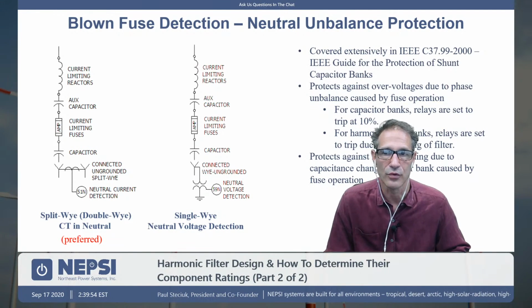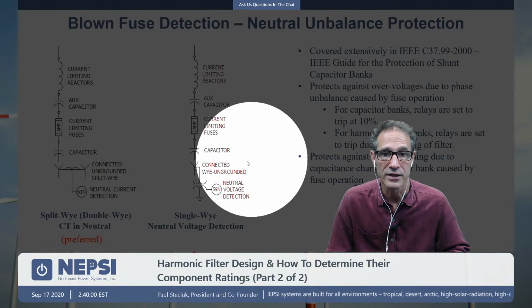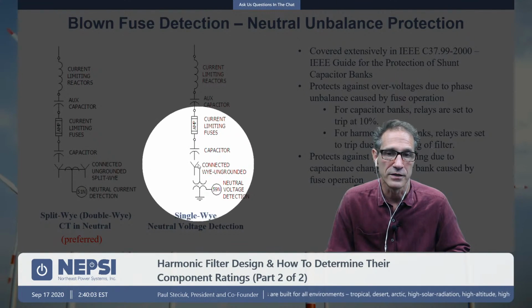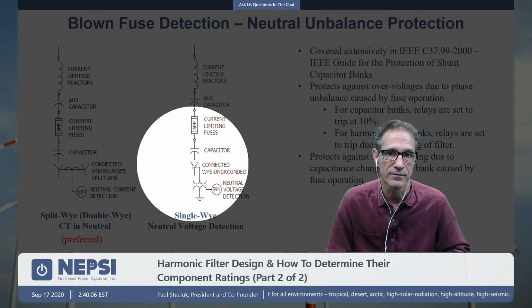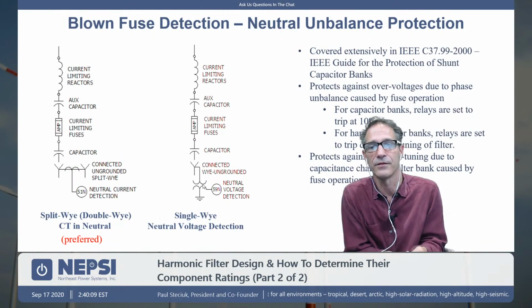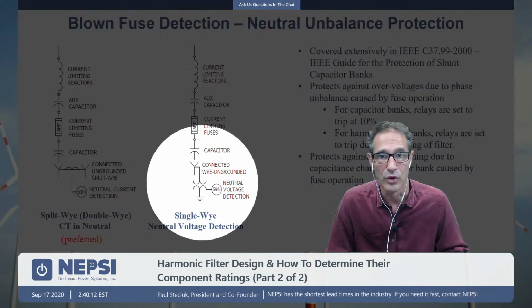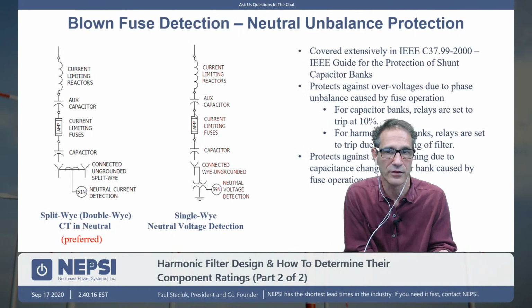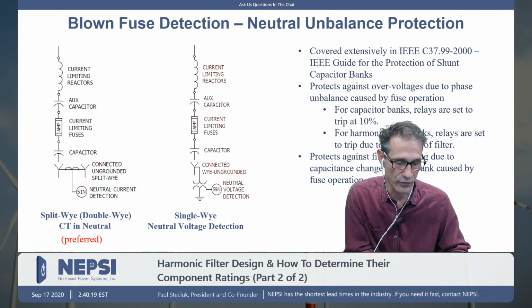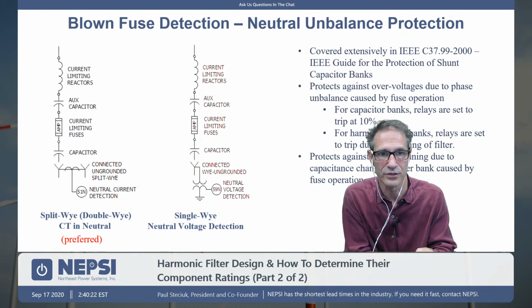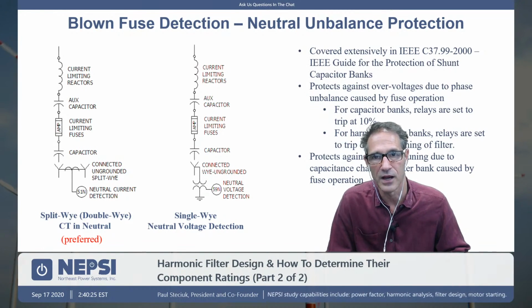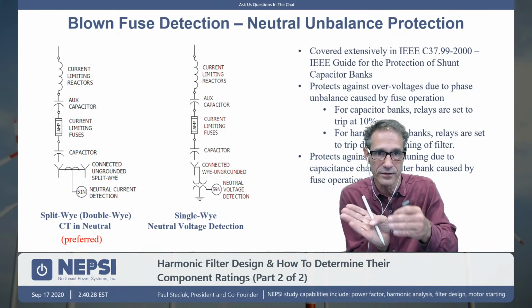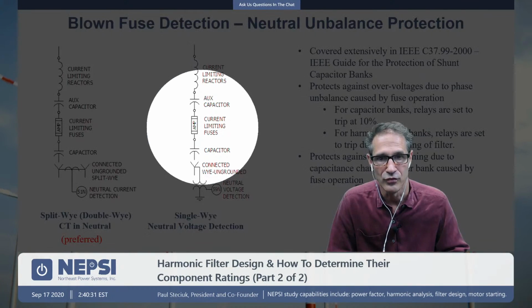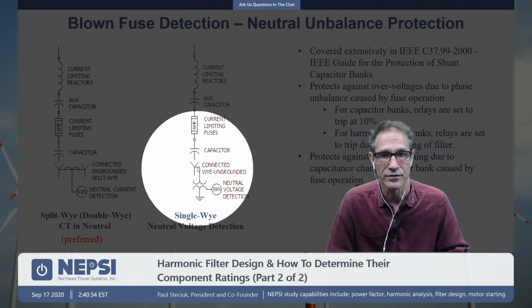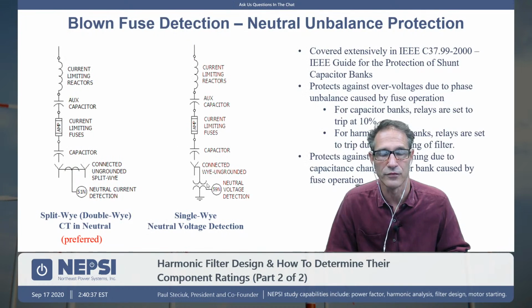The capacitor banks, there's always some type of blown fuse detection built into it. We talked earlier about a single-wye connected bank. That's actually shown here. We put a PT in the neutral. We're looking for a voltage here, a neutral to ground, to determine if a fuse has operated. So under normal situations, phase A, B, and C, the capacitor values are equal, the reactor values are equal, and therefore the neutral to ground voltage will be 0 volts. If instead I operate one fuse and I create an imbalance within the capacitor bank itself, I will get a neutral to ground voltage that can be detected with a neutral PT here. So that's called neutral voltage detection.